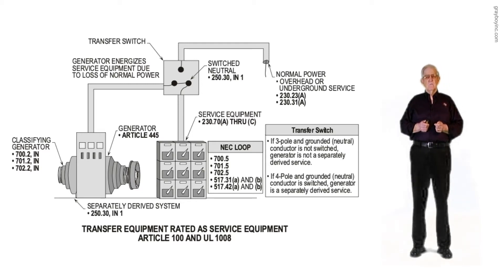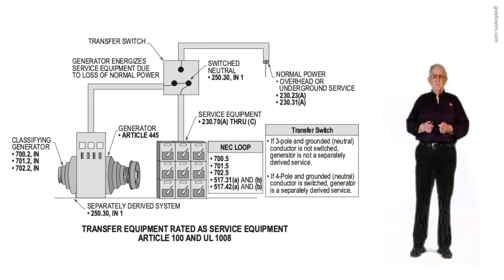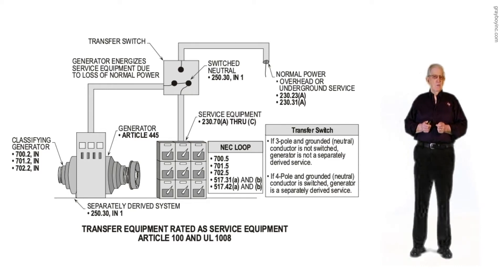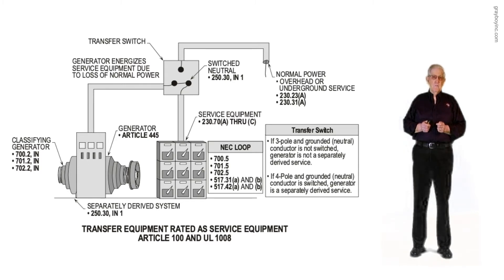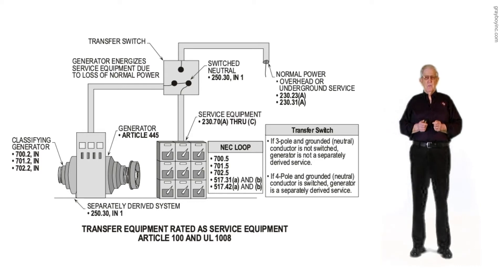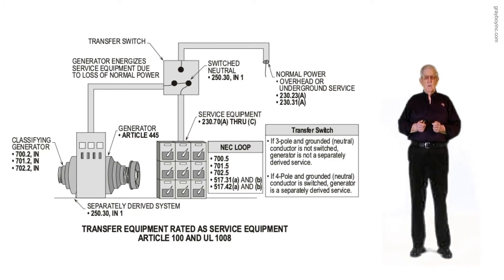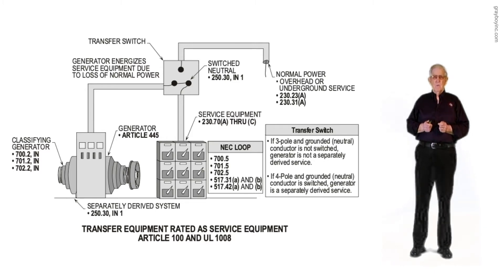There are some advantages based upon the classification of your generator. Notice 445.13 basically states if you size the conductors from a generator at 115 percent of the output of the generator, then the disconnecting means could be located remotely from the generator. But if you did not size the conductors at 115 percent of the output, then you would install a main at the generator.